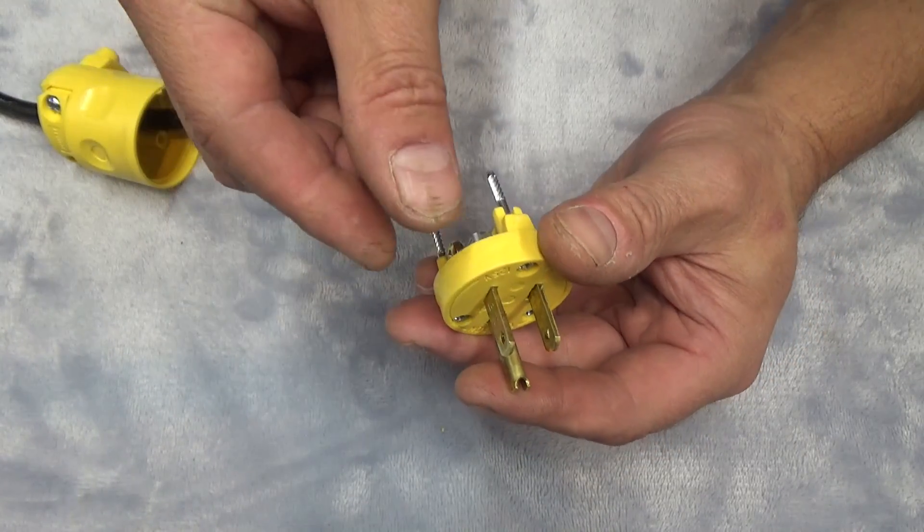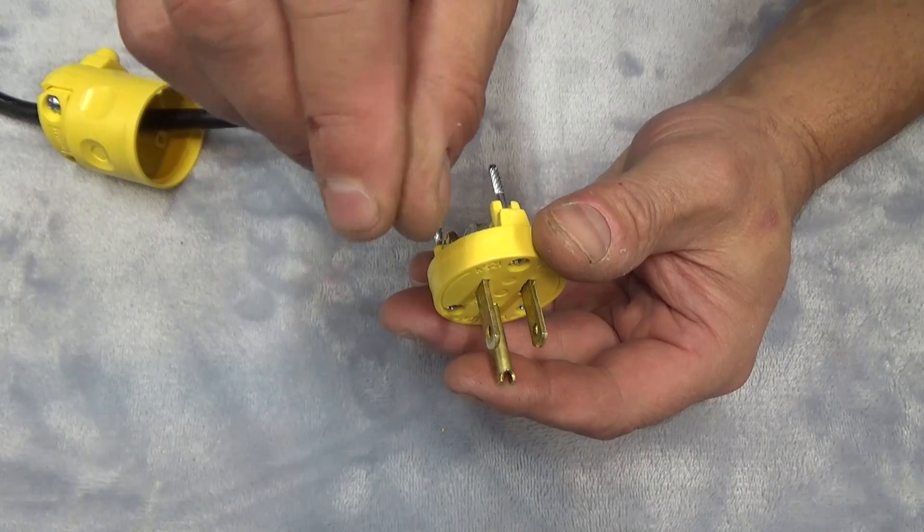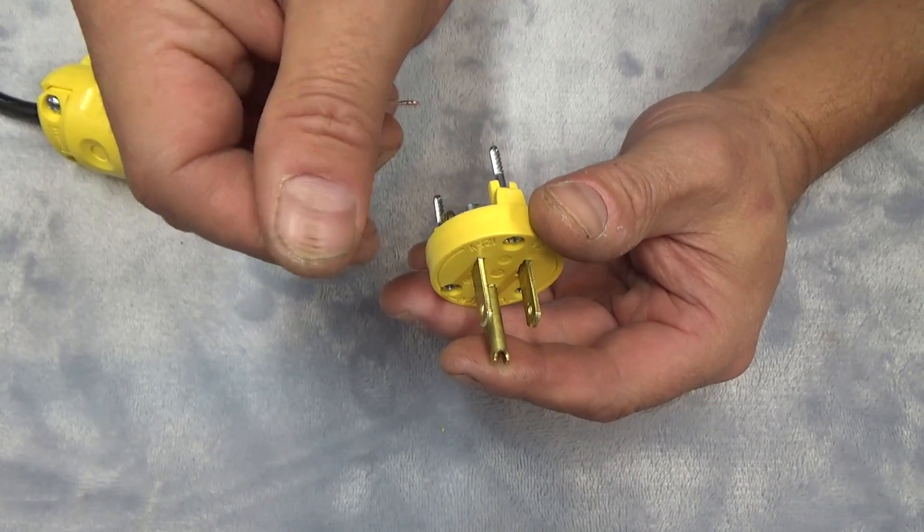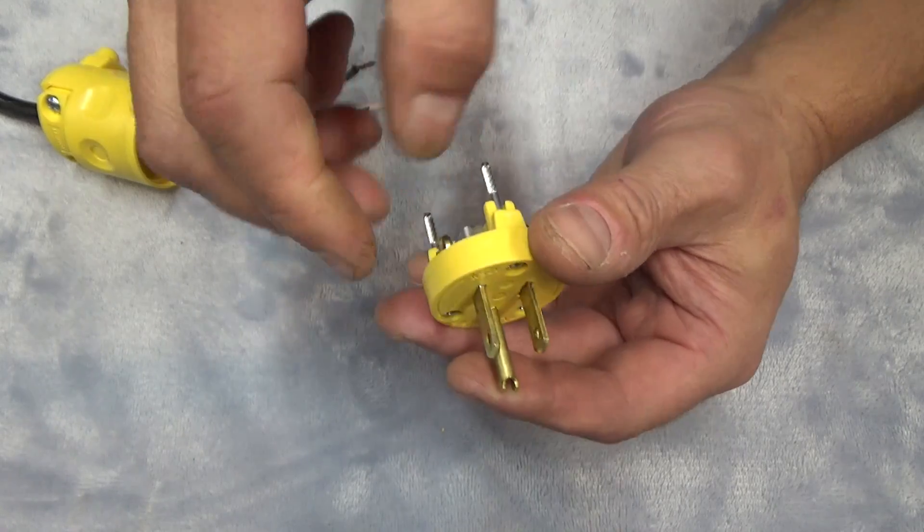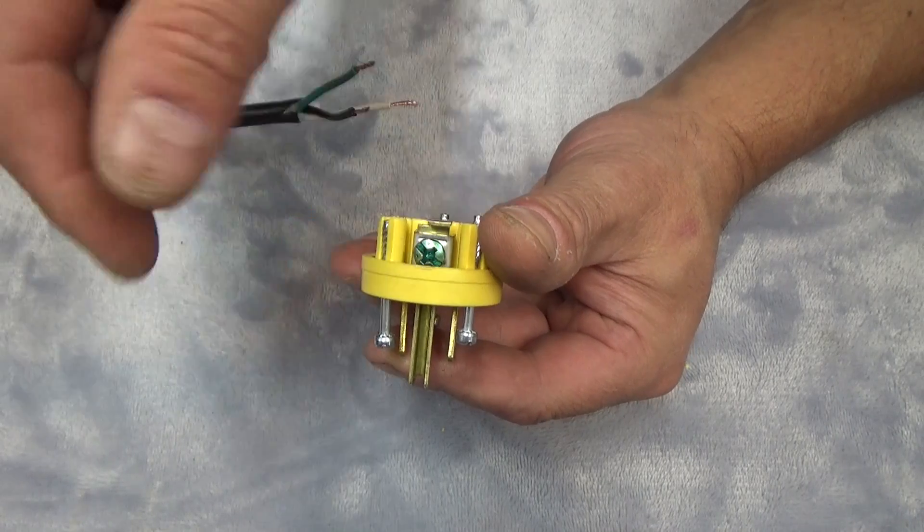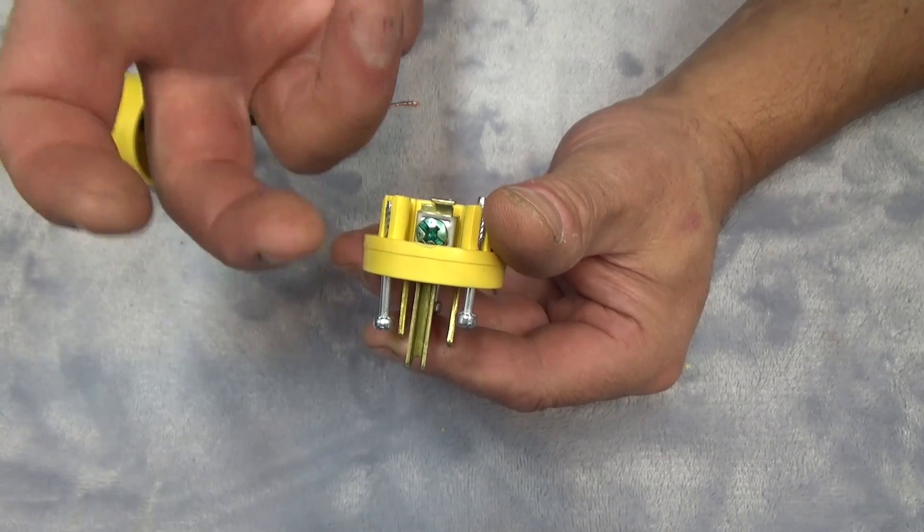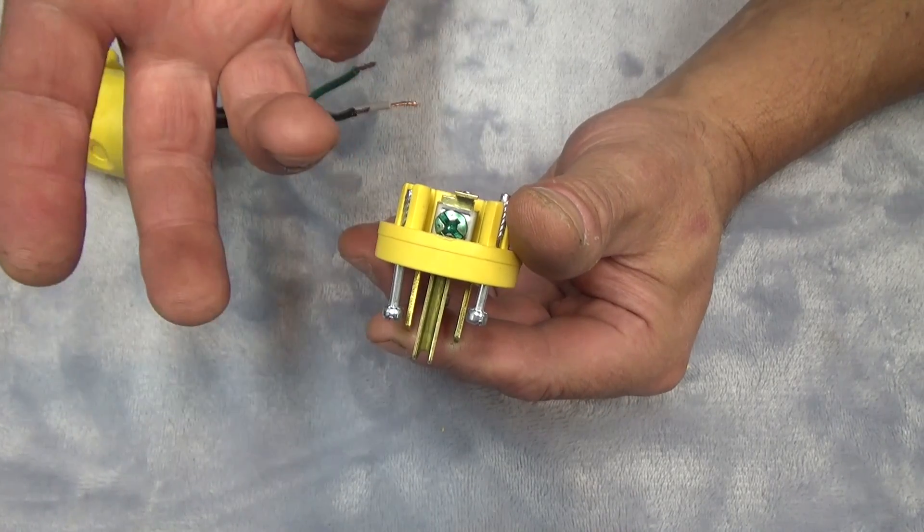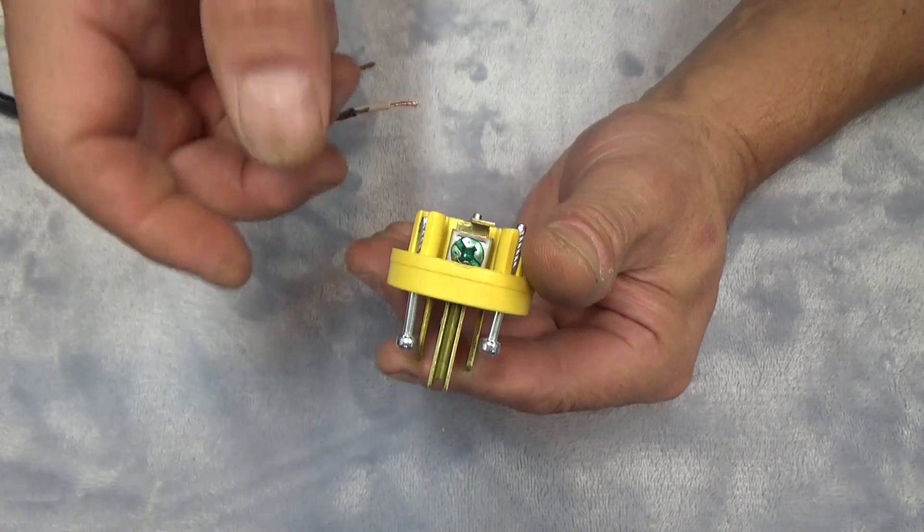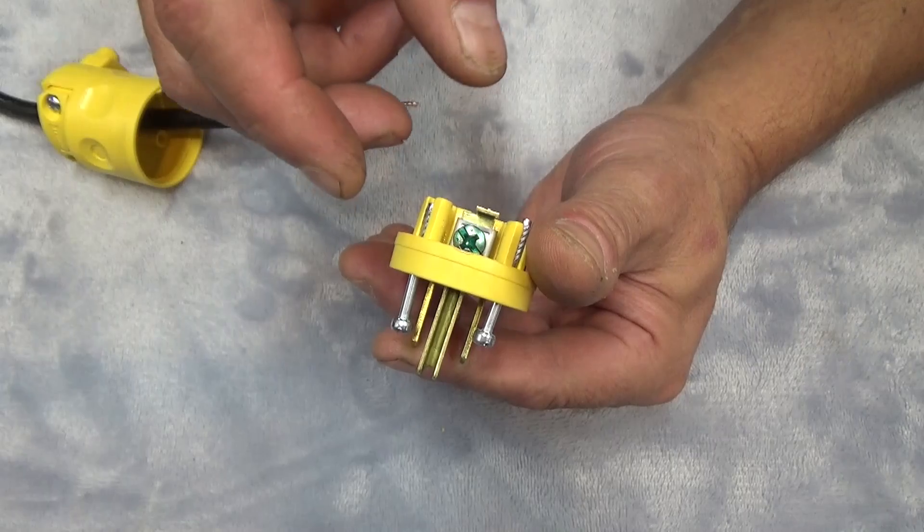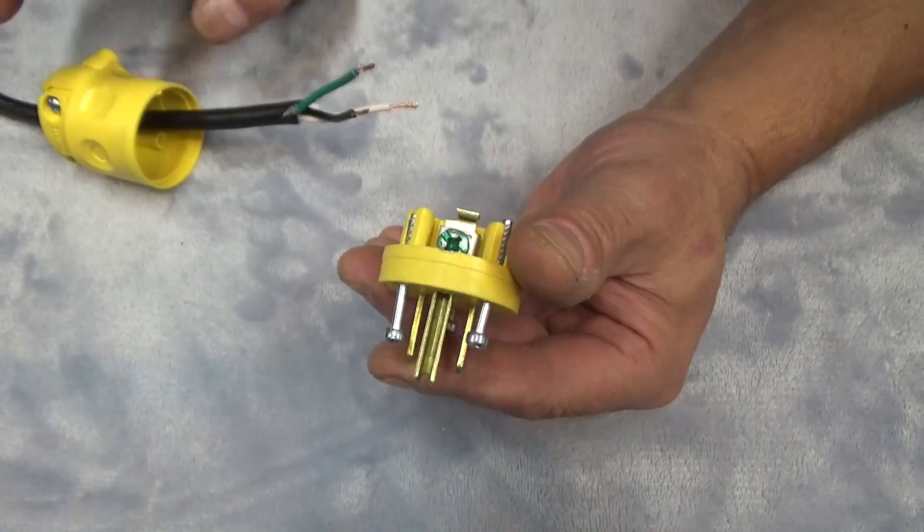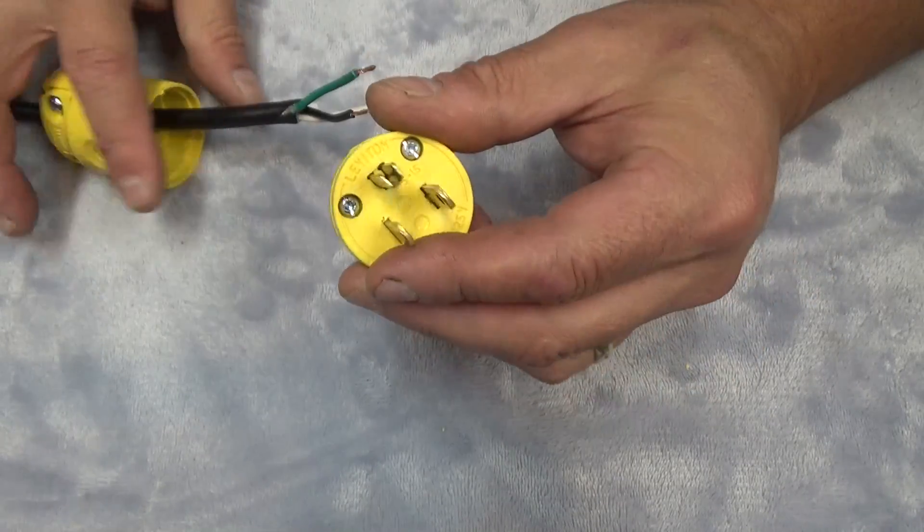So you could be sending current through the wire that's supposed to be attached to neutral, which means if you have a switch on that fan and the switch cuts the black wire or the current going to the motor using the black wire, and we have this reversed, it would be cutting the neutral, which means that current would be sent through to the motor, which means that it could be charged. There's just no path to complete the circuit because we've cut the neutral. But if you were to say working on it, which hopefully you'd unplug it, there would be power to it. And you may think that it's not because the switch is off. So that's the secondary functionality of this.